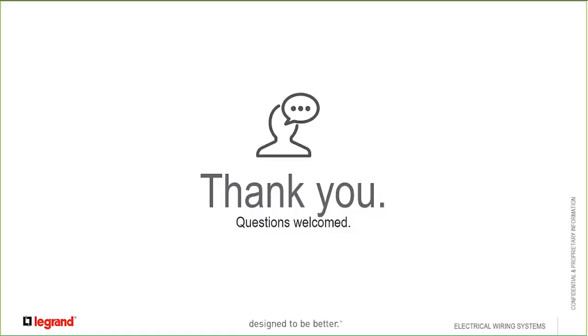Okay. There was another question that I think would be good to just roll into: how often do GFCIs need to be replaced? So today's GFCIs have, like I touched on in the presentation, an end of life, a series of events that could happen that could determine that it's end of life. Most of them will show either a solid red light, other manufacturers may be different, but you'll see a visible indication that the GFCI device is no longer protecting the receptacle. With today's standards, a lot of companies have different ways of attacking this. We call ours our safe lock protection, but if any of the critical components in the GFCI device fails, power to the face of the device will be denied, and there will be a visible indication telling you that you need to replace that device.